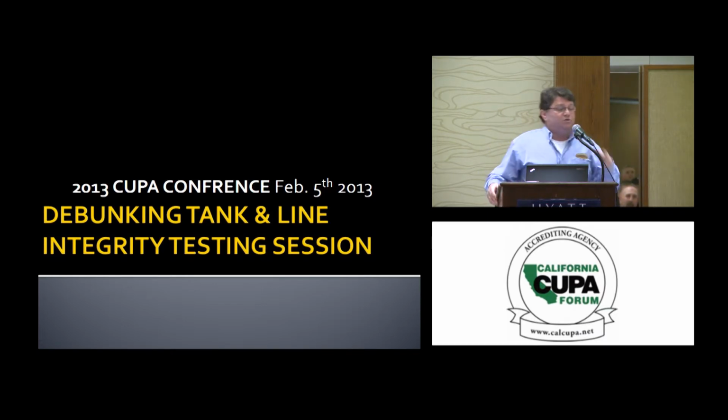So when Petrotite came out, the rules in 1988 said you'd better be able to handle temperature. We handle that by circulating the liquid. The philosophy is that you have stratification in a tank. You've got red marbles and blue marbles. If I circulate them together, I'll make purple marbles. That was the premise. We wanted to get the average mean temperature in the tank and then correct to 60 degrees using the coefficient of expansion. Thermal dynamics of liquids were taught. You talk to technicians today, they look at you with a blank stare. What is that? Okay, science.